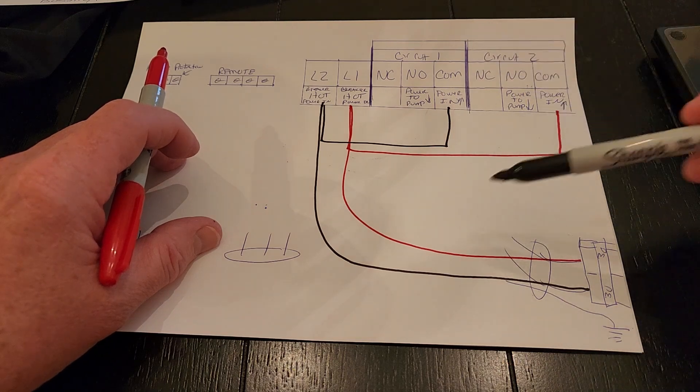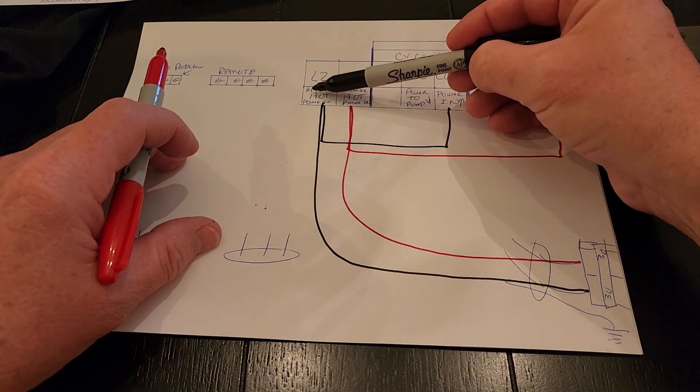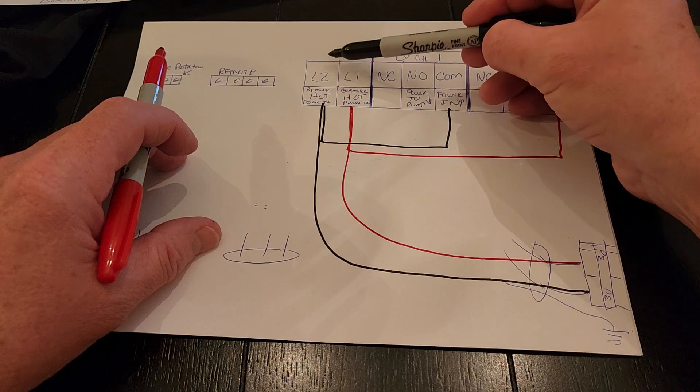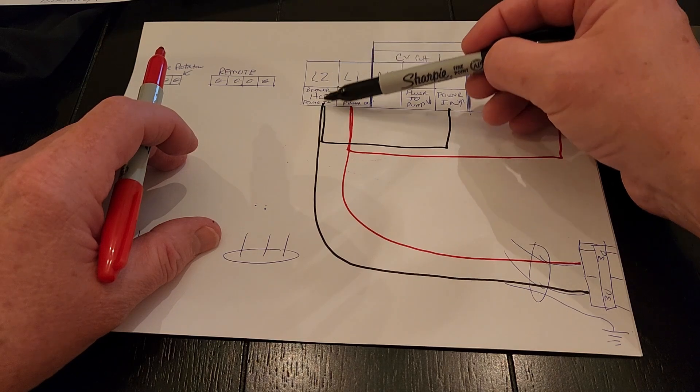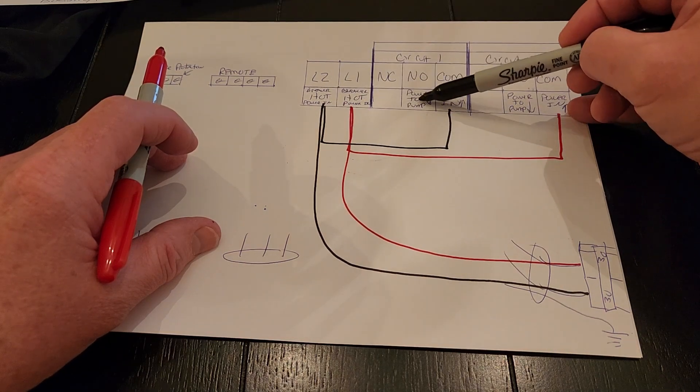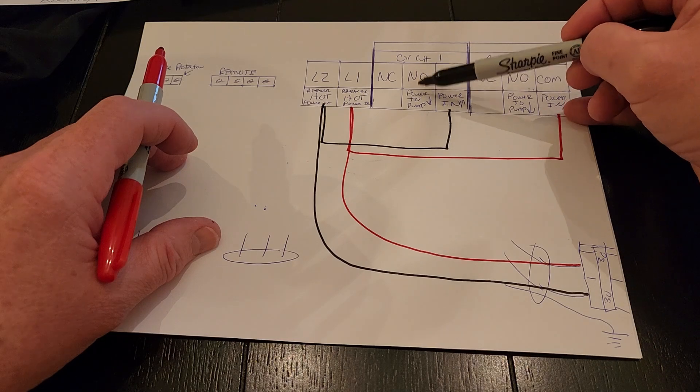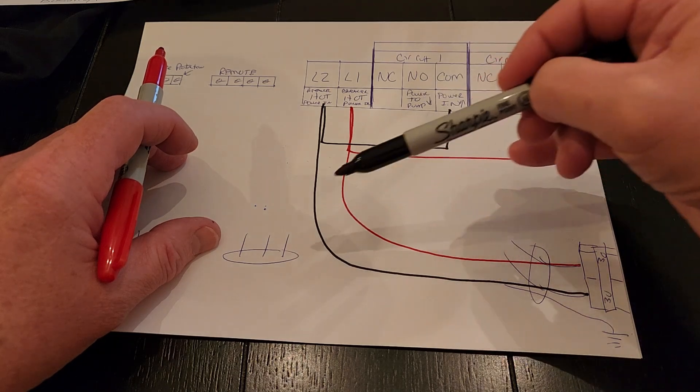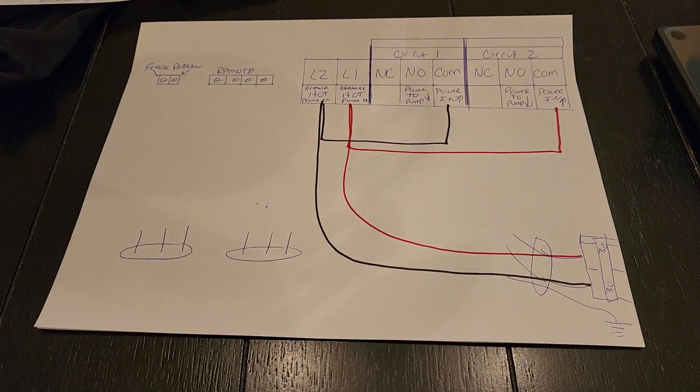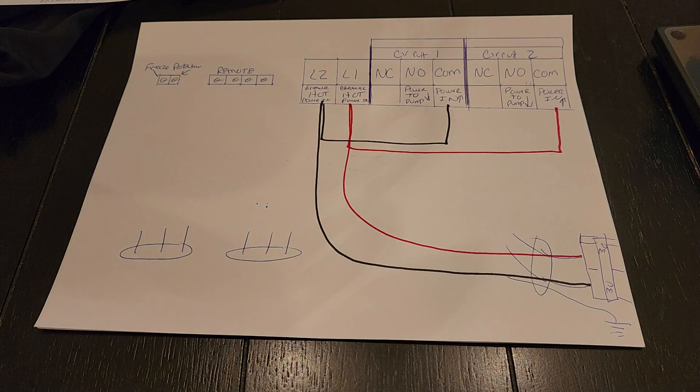Like I said, power comes into the box here, goes to the relay system, and then when the pump turns on, it comes out of L2, powers the relay, which turns on normally open, makes it closed, which sends power to the pump. So that's how you get power to the circuit.